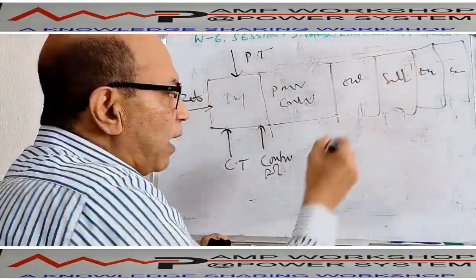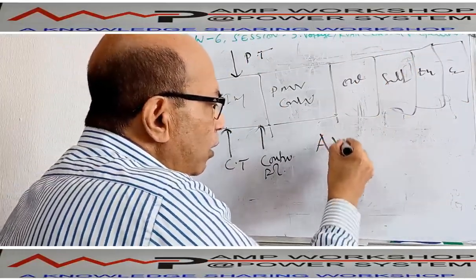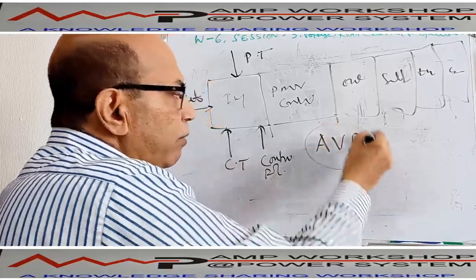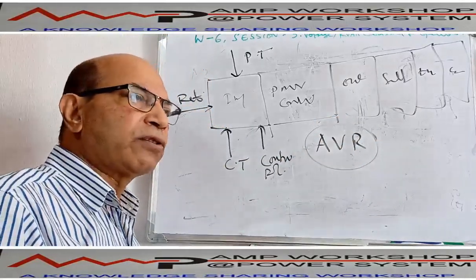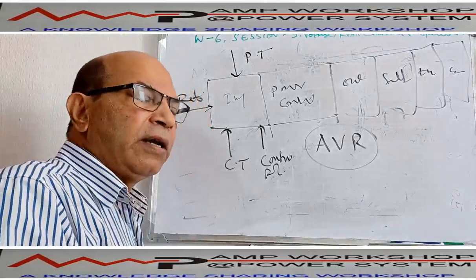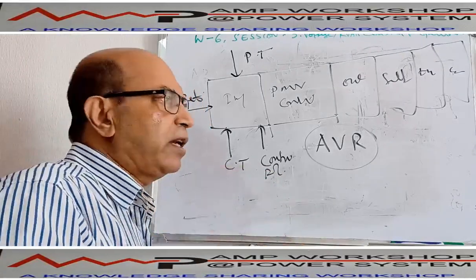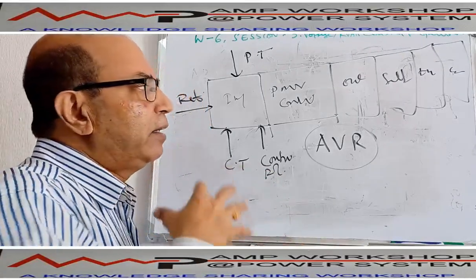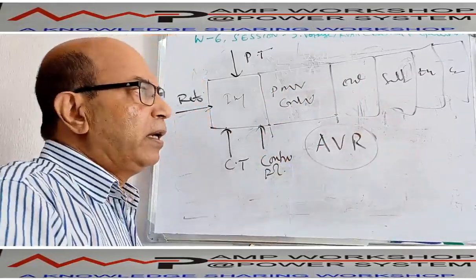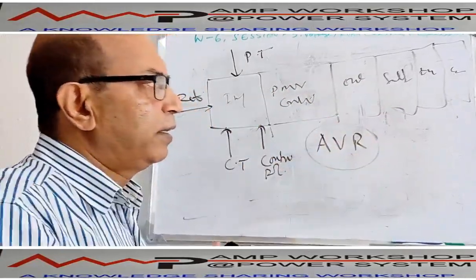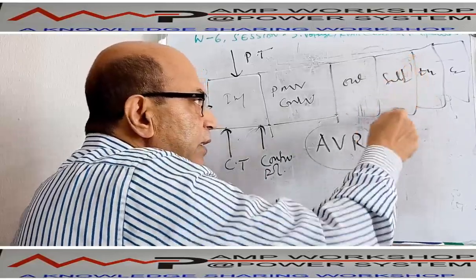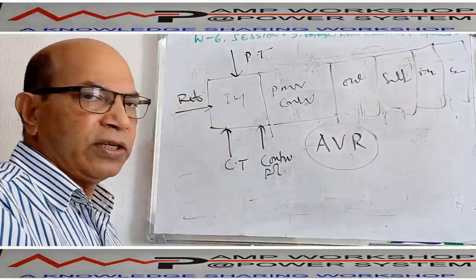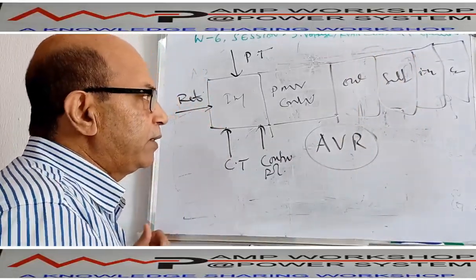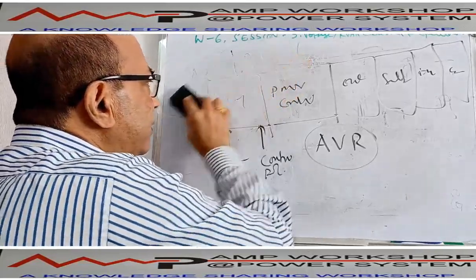Okay. This part we call the automatic voltage regulator. This automatic voltage regulator is doing this job, it is controlling the generator terminal voltage. Indirectly, it is controlling the excitation of the exciter and doing this job. Now, this AVR, we have multiple settings in the setting section. So that we'll discuss in brief. What are the various settings available in this AVR?